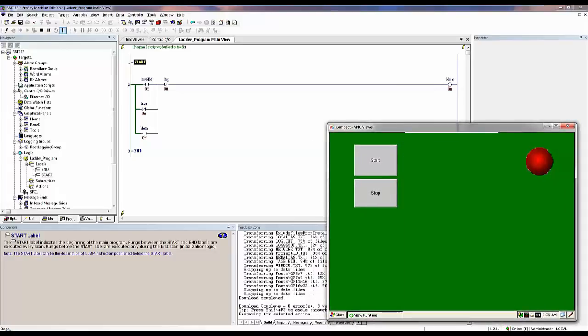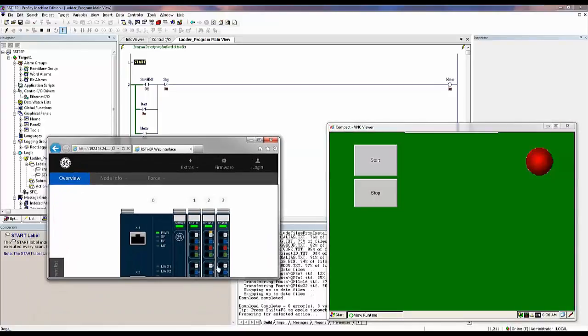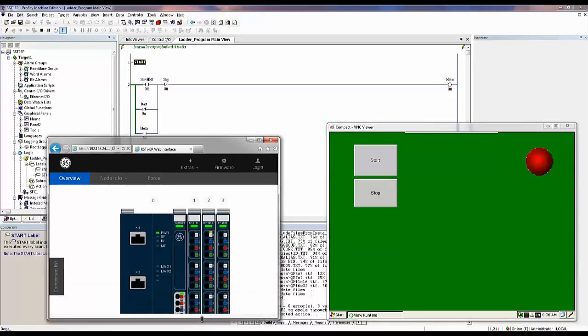So if I hit the start button here from the HMI, we can see that it started at the top, we sealed in the circuit, and the motor stays running. We hit the stop button, it drops it out, so we can see that working. We also have down here, I've got the web interface showing my RSTi-EP and the output card right here.